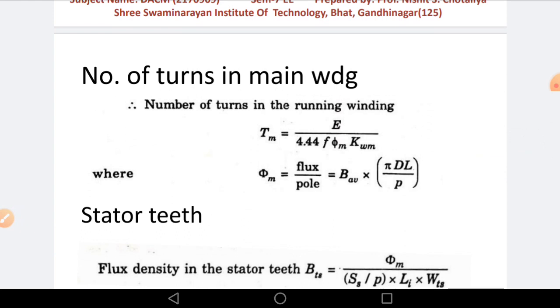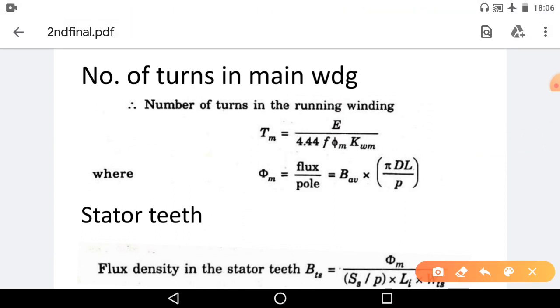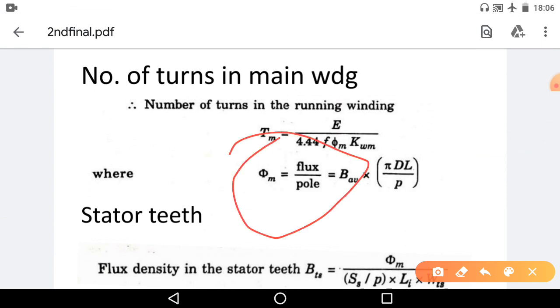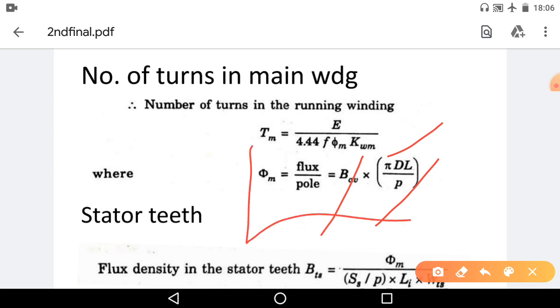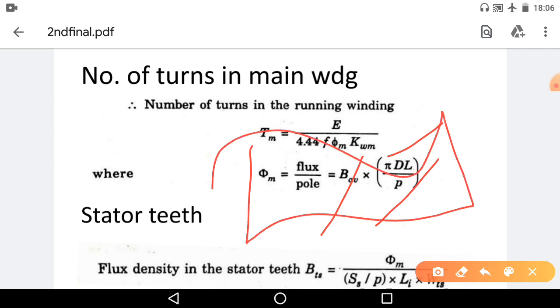So the stator turns equation is: T = E / (4.44 × F × φm × Kwm). And φm — the flux per pole — has the equation: φm = Bav × πDL / P.